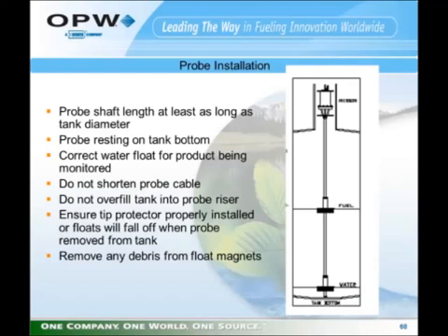Need to ensure that the tip protector at the bottom end of the probe is installed securely so it doesn't fall off. And periodically, you would want to remove the probe from the tank. Check to make sure that there's no debris stuck to the magnets. Make sure that the floats have free movement up and down the probe shaft. The only actual annual maintenance that we recommend is that the probe be removed from the tank at least once a year and the shaft cleaned and inspected for debris.